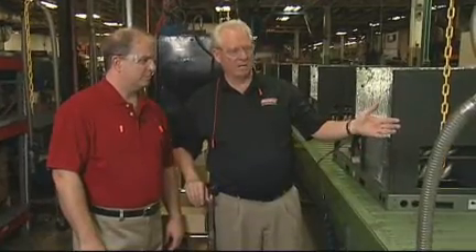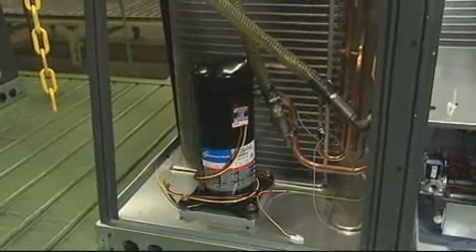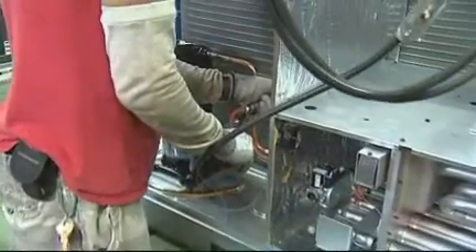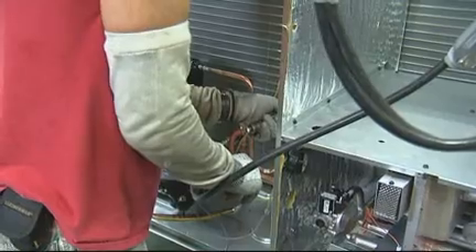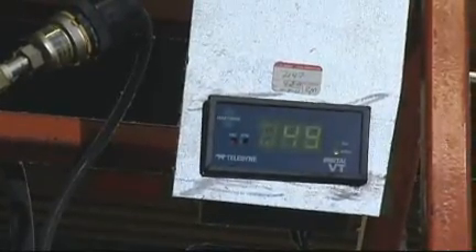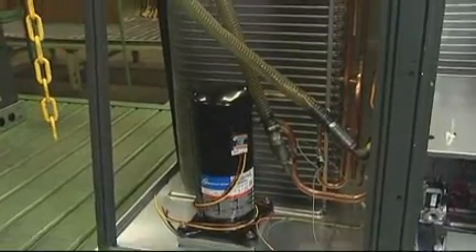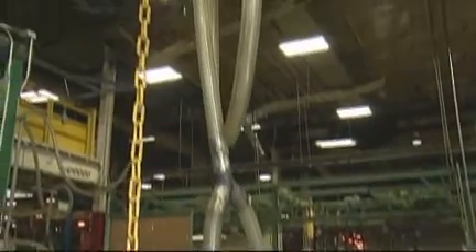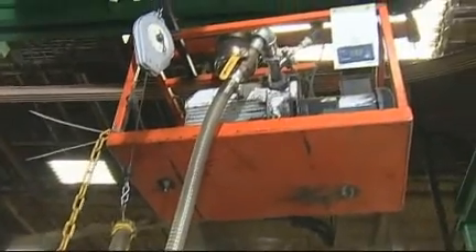Okay, Mark, we're at the point of the line now where we've got a complete refrigeration system. Right. It's all brazed together. We've done a high pressure burst test to make sure there's no weak spots in the system. Sure. Then one of the most important elements of making sure you've got an effective refrigeration system is the evacuation of any moisture or any contaminants. Right. You see overhead, we've got these vacuum pumps that move along with the line. You see that gauge up there? The vacuum has to be drawn down to 100 microns or better, because having a clean system before we charge it with refrigerant is the key to quality.